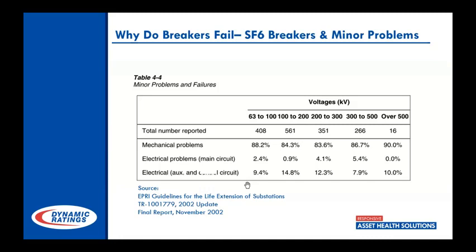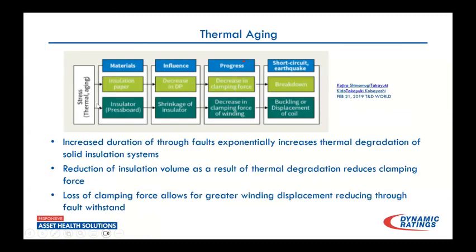So that is fault current that transformer is accumulating in that line. And you could have 4 to 6 distribution breakers. You get a couple of bad ones in a fault prone area, and that transformer is seeing a lot of duty that it really should not see. So what's that do to our transformer at that point? Well, this was something I found in T&D a while back, and I really thought this was the best explanation of how that's affecting the transformer.